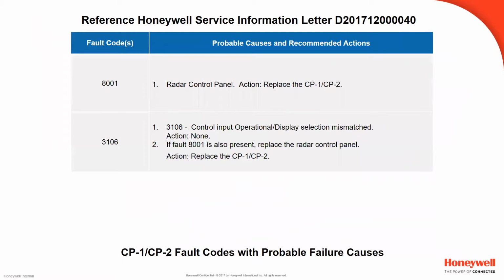Right. The control panel has two faults, 8001 and 3106. The 8001 fault gets logged due to control panel internal failure, and it could be a combination of all of the detectable control panel faults. And if there is a hard failure of 8001, then the control panel would have failed and not the RP. And we recommend the first troubleshooting is to check the control panel functioning and replace if necessary.